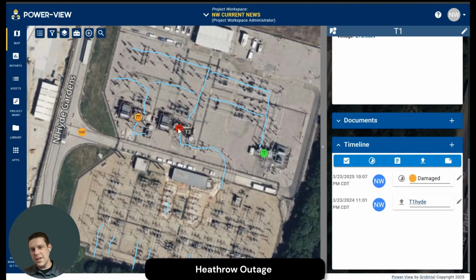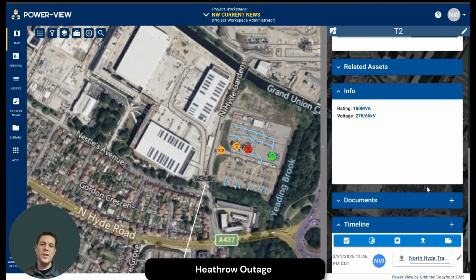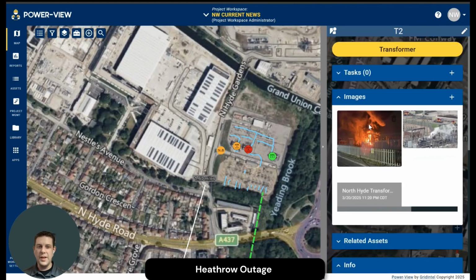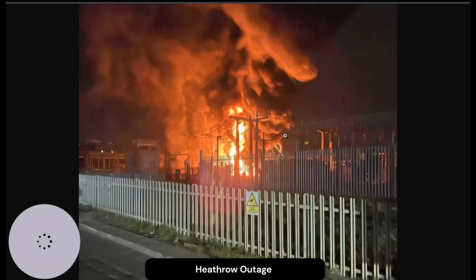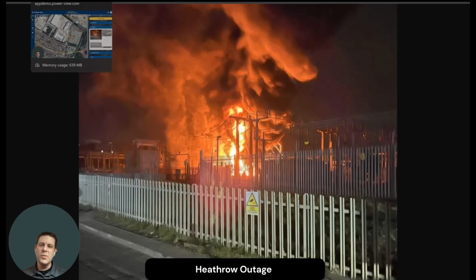Looking at this, T1 and T2 - this is where the source of the problem occurred. A massive fire occurred Thursday night, and here's a picture of it. Basically, these transformers can have an internal fault occur in or around the metals inside - coils of copper conductor with paper. It's an electromagnetic force, so it's physics, and whenever you have this much energy moving, you can have heat.